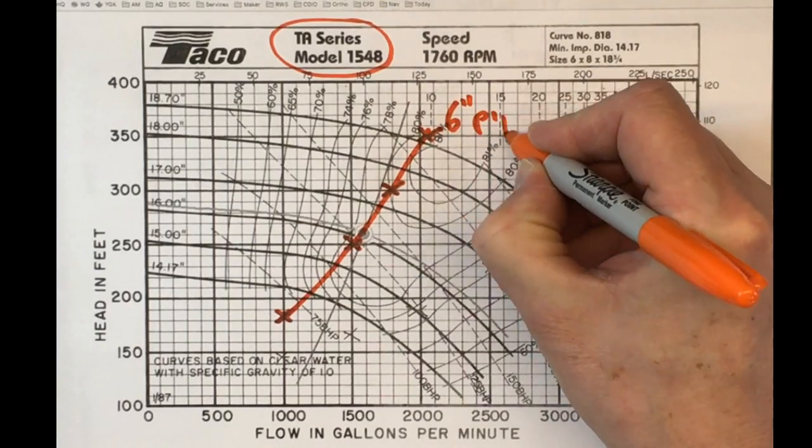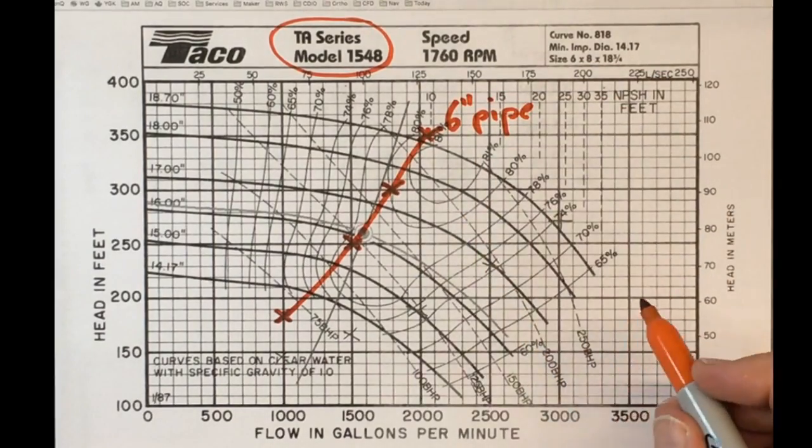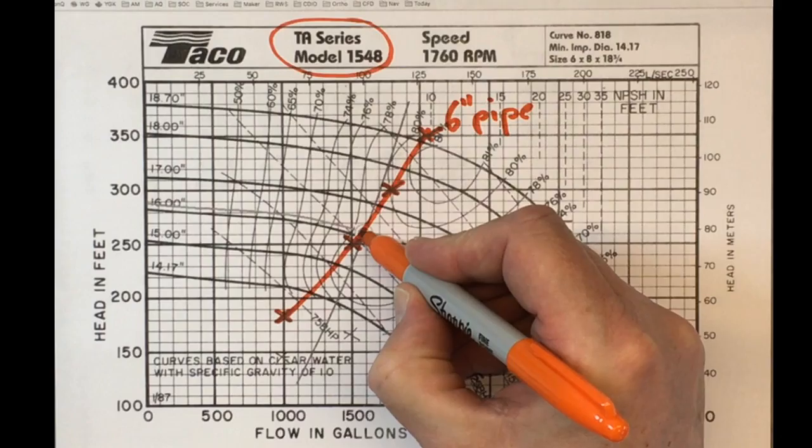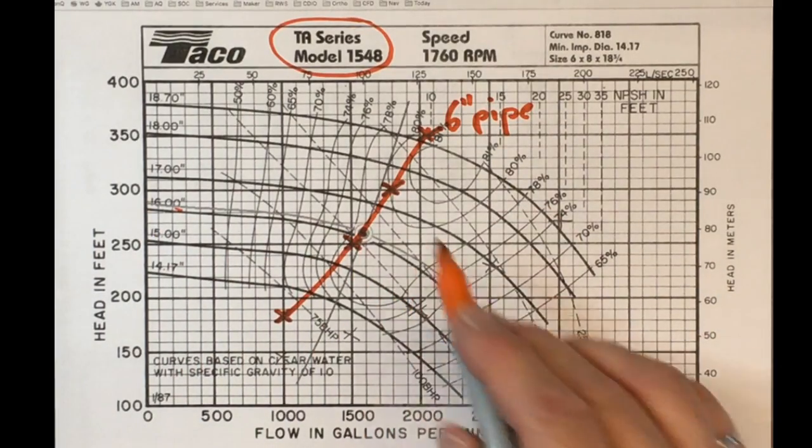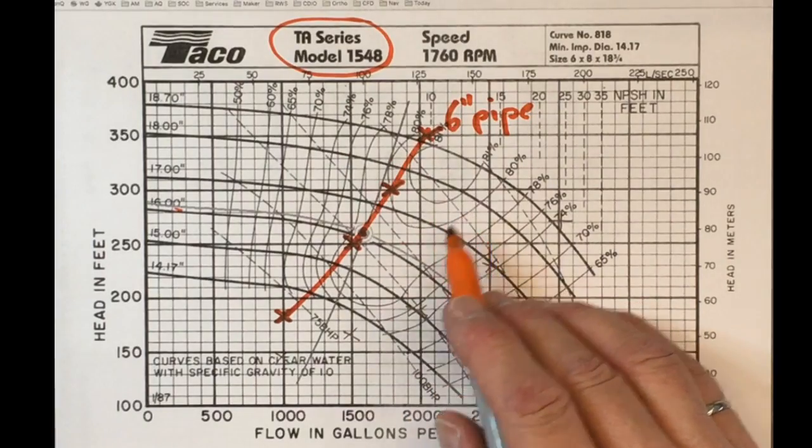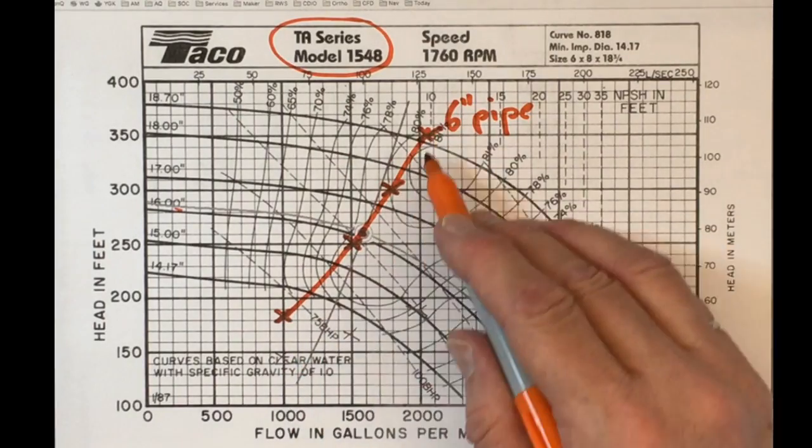So there's our 6-inch pipe solution, and it goes through this operating point for the 16.3-inch impeller that was the suggestion from the selection system. So that's encouraging. It's doing about the right thing.